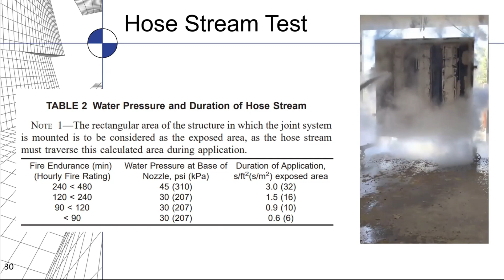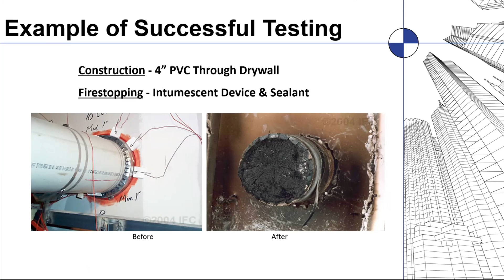So this is a PVC pipe. On the left you see the cold side — there's a firestop collar in place and a pipe running through that opening. All those little wires are temperature gauges, thermocouples. After the fire, on the hot side, the opposite side where it was burned, you can see where the pipe has melted away and the intumescent has completely filled that cavity.